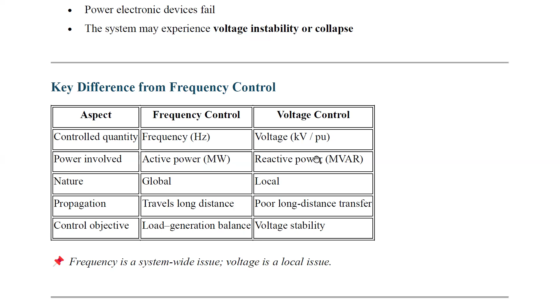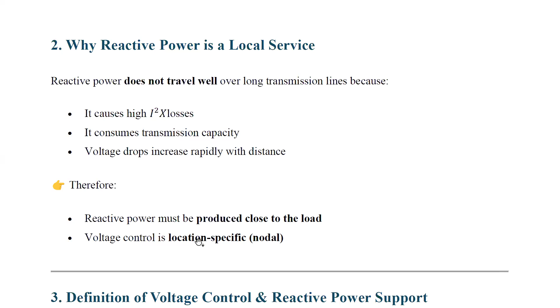Next, why is reactive power a local service? Reactive power does not travel well over a long transmission line because it causes high I square R and I square X losses. That means I square R resistive and reactance losses. So it consumes transmission capacity. Also, voltage drop increases rapidly with distance. Therefore, reactive power must be produced close to the load, whereas voltage control is location specific. That means nodal. In that particular node, it is location specific.